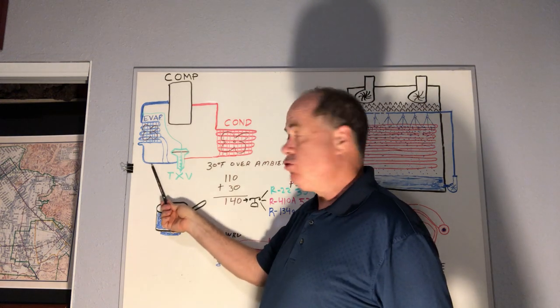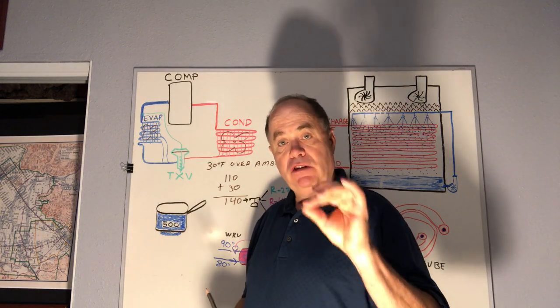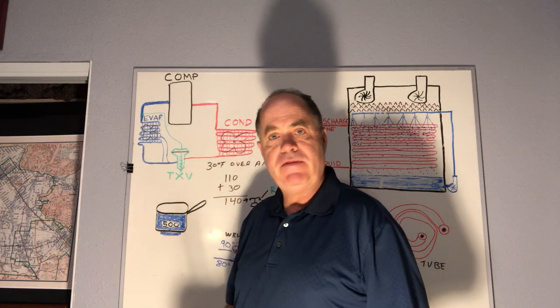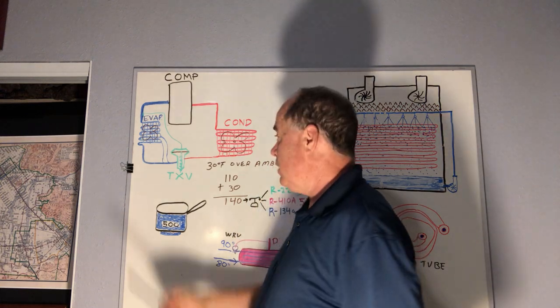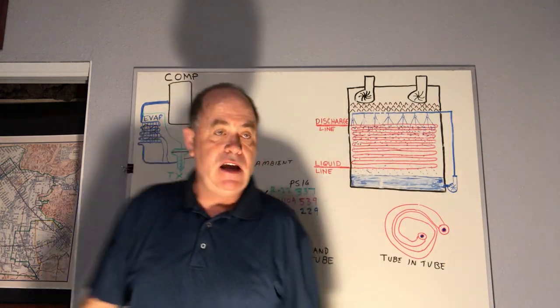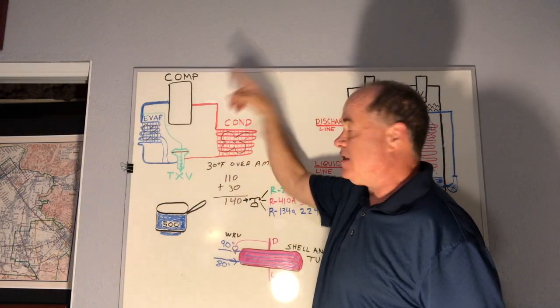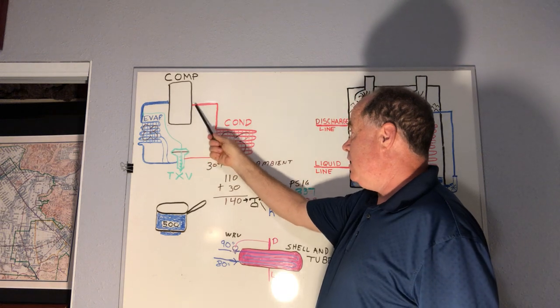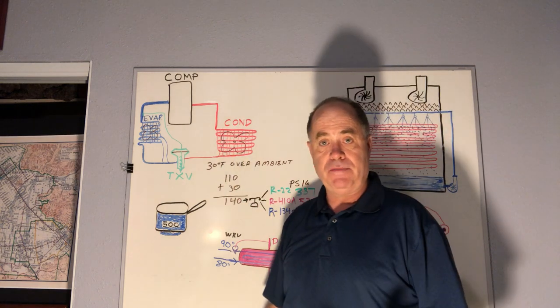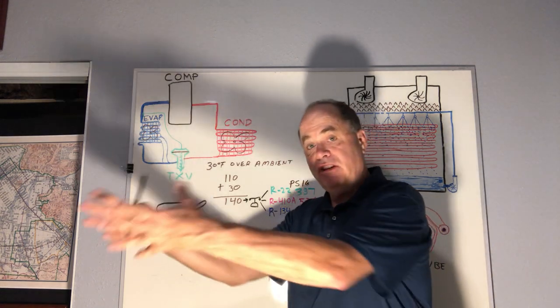As the refrigerant travels into the evaporator, it's a low-temperature, low-pressure liquid with a little bit of vapor. As it travels through the evaporator, it absorbs the heat from whatever we're trying to cool down — like your room or zone. Then the compressor sucks it from the suction line and sends it out the discharge line. That discharge gas is hot. As it travels down the discharge line, it desuperheats, and then it comes to our condenser where we dump the heat into a place we don't care about — generally outside for a window unit or central AC system.